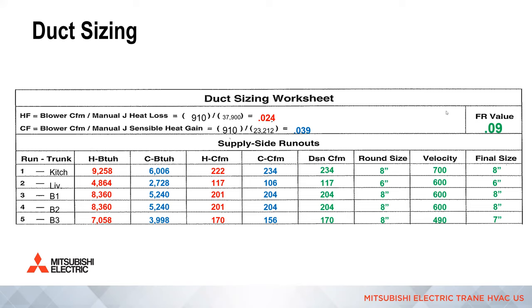Great. And then Steve had a couple more questions related to the calculations. Oh yeah, I see them. So the 37.9 was actually pulled out of Manual J version 8. Normally if I was to do a full 4-hour design class, we'd go through Manual J, get the report, and use that report as we go. With just Manual D, we have to assume you did the load calculation and took those numbers in order to do the D design. So yes, it would have come out of the software model. And then where the 910 came from. Yes, 910 CFM was our medium volume of air.